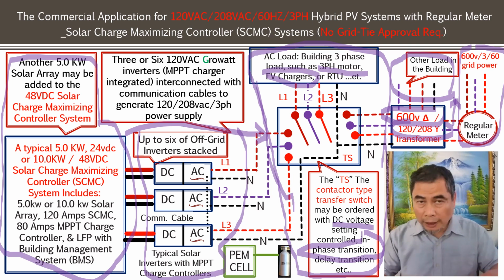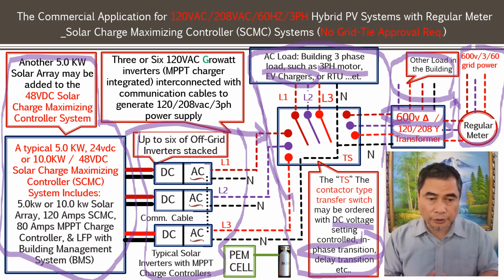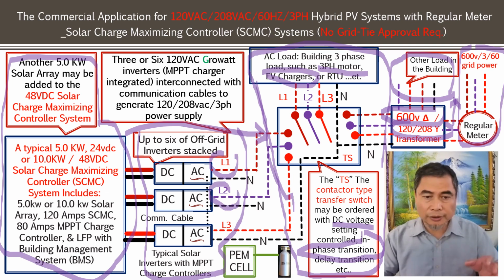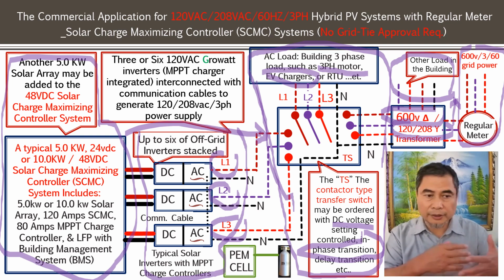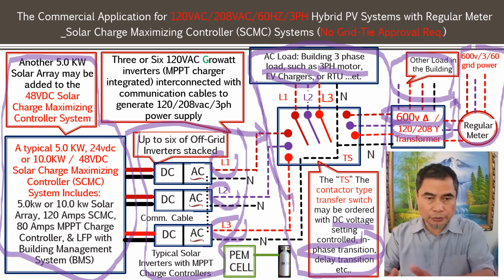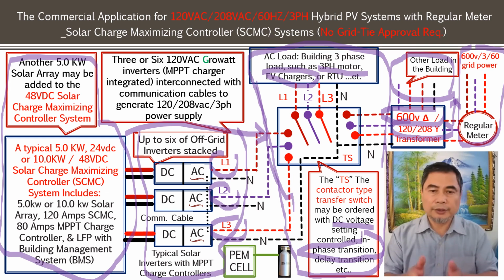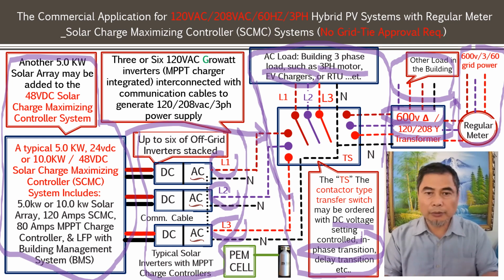A typical setup is 6 single-phase 120 VAC inverters: 2 joined together take care of one phase, a second pair joined together makes another phase, and another 2 joined together make a third phase. The DC side can be a 24 system or a 48 system, and they can produce this three-phase power off-grid to power the load.